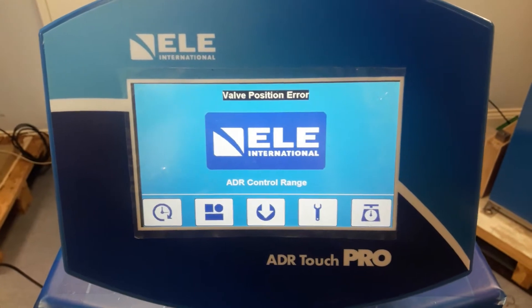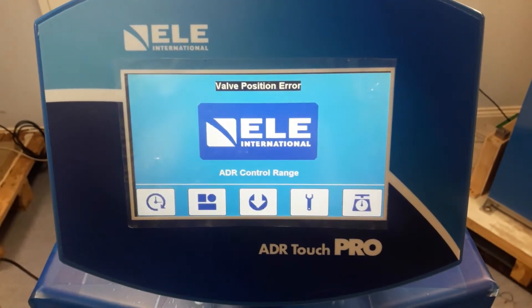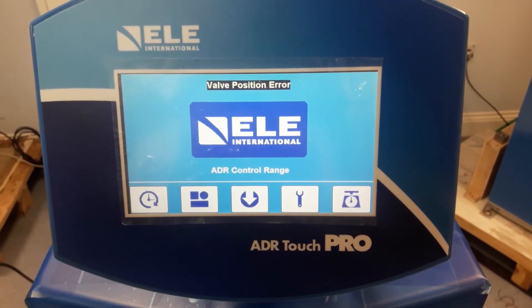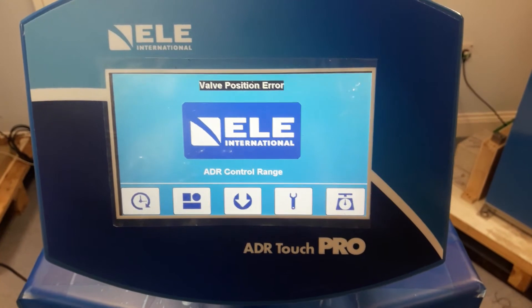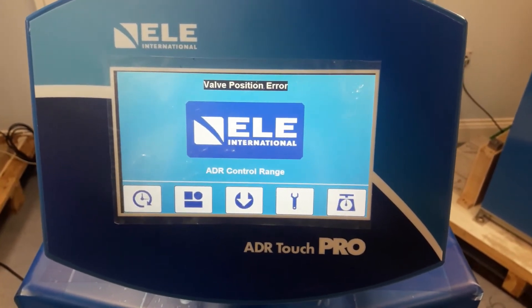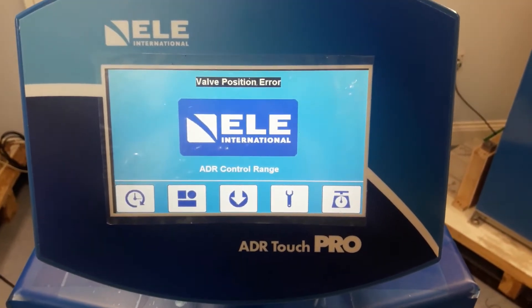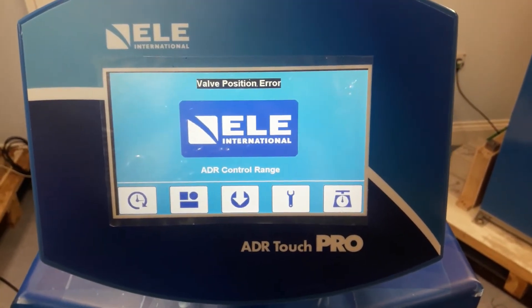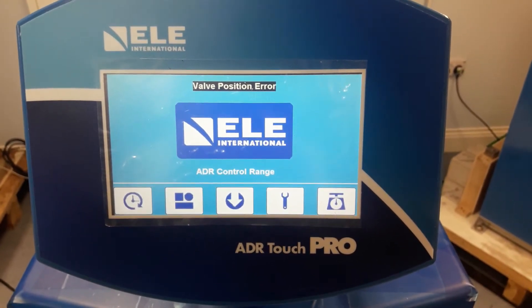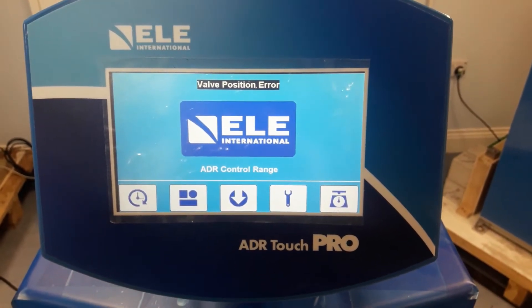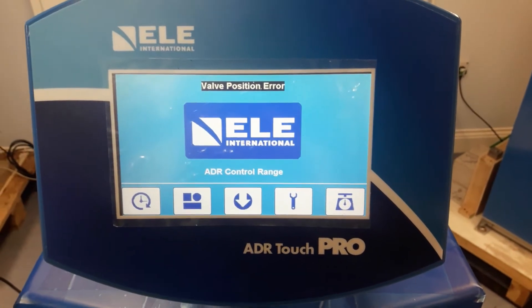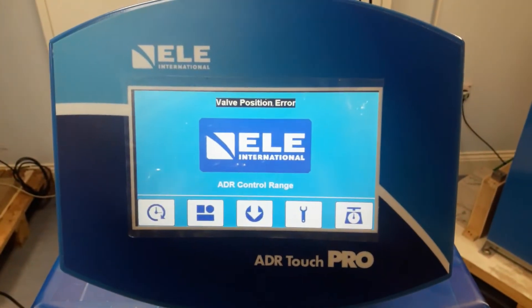I'm going to show you how to reset the valve position error. The valve position error relates to the home position of the stepper motor assembly, which controls the loading of the pace rate. Occasionally this would be a real error — sometimes it's because the machine has experienced an electrical issue or something else has gone slightly wrong.